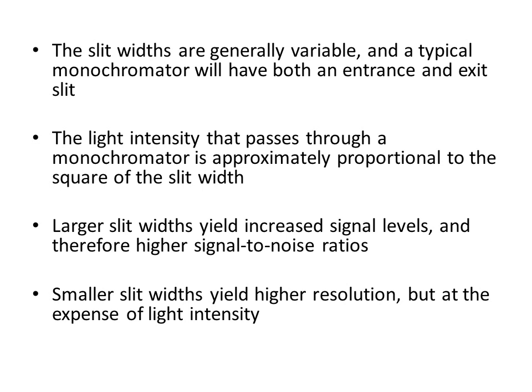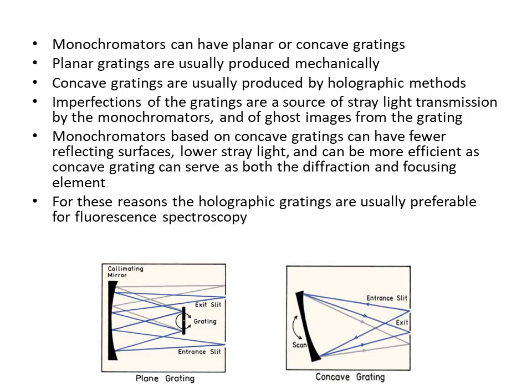Larger slit widths yield increased signal level and therefore higher signal-to-noise ratios. Smaller slit widths produce high resolution but at the expense of light intensity — the light intensity will be lower. Monochromators can have planar or concave gratings.